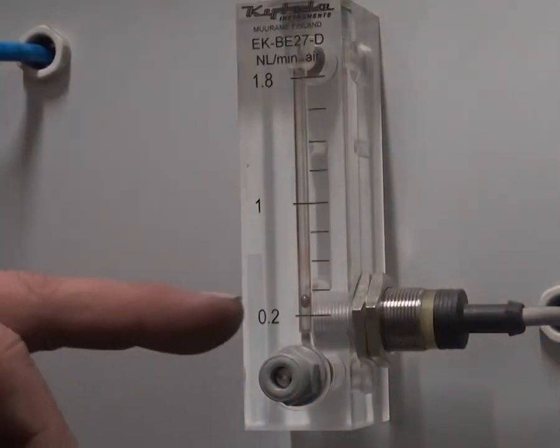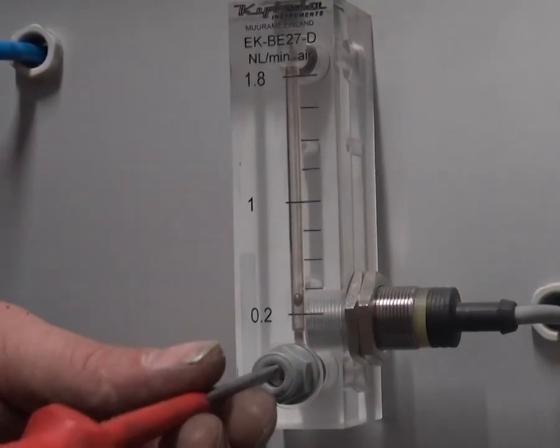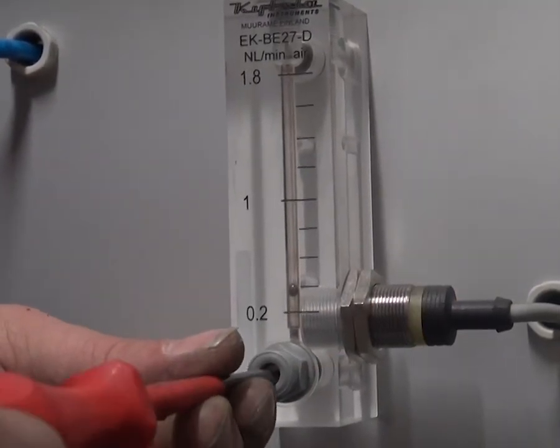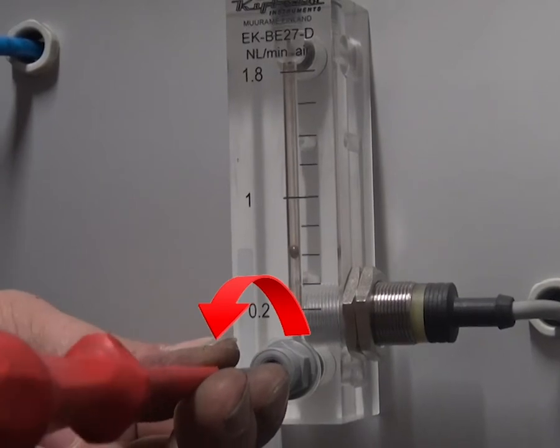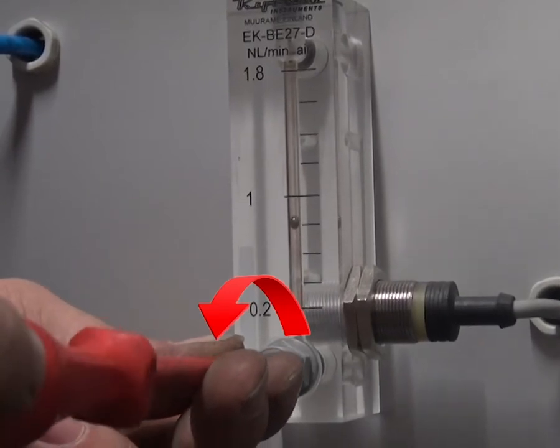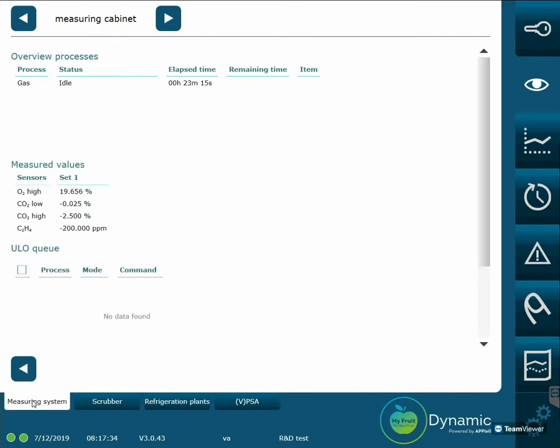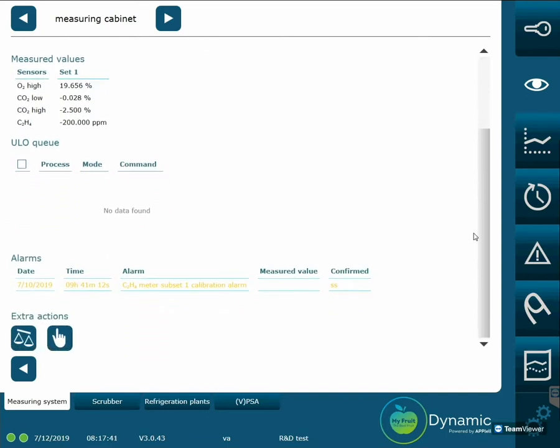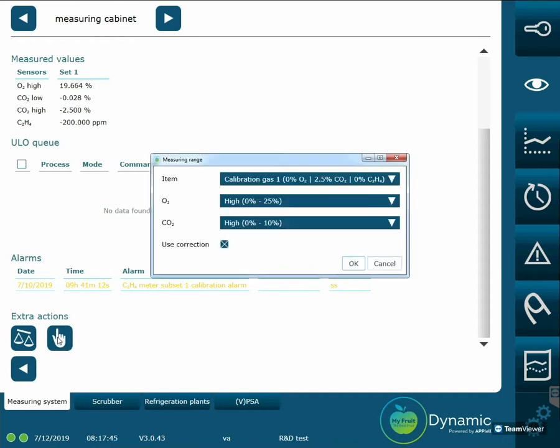This flow meter is indicating that the flow is too low at the moment. You can adjust the flow by turning the screw to the left, to make sure the bubble levels the number 1. Now you have to go back again to the tab, Measuring System. Scroll down the page till you see the icon with a hand on it. Click on the icon and make sure the mode has been set on Calibration Gas 1, and press on OK. The pump will now start running again.